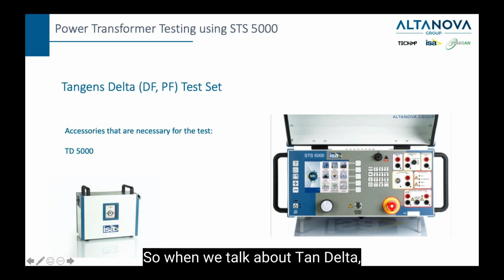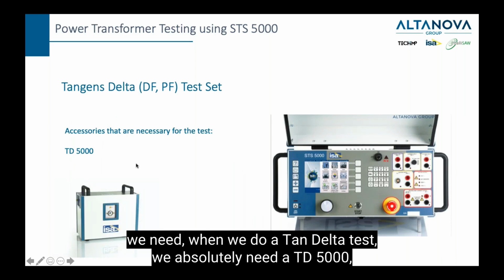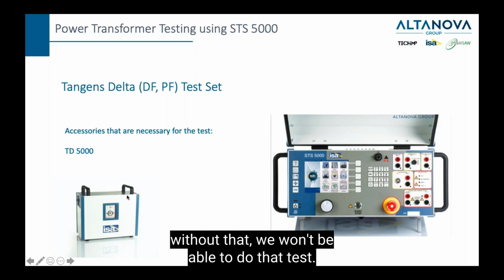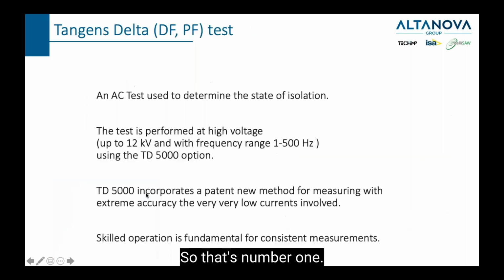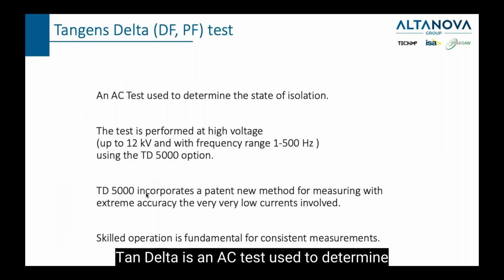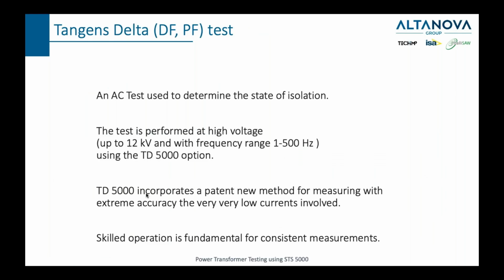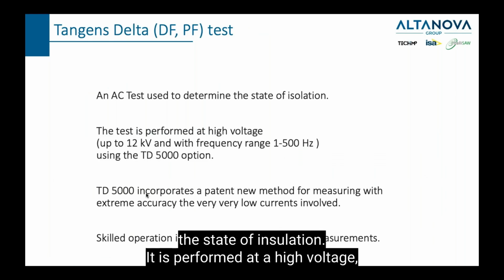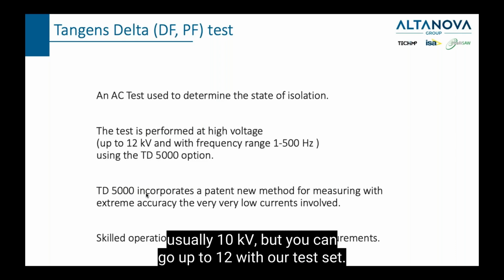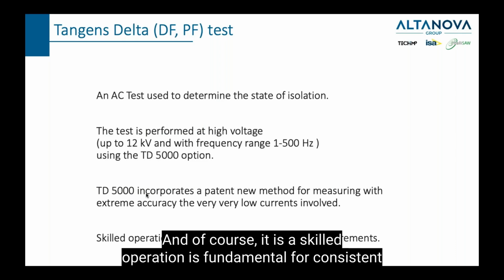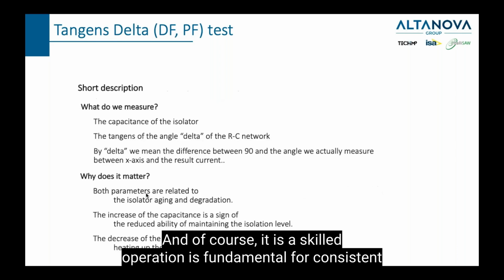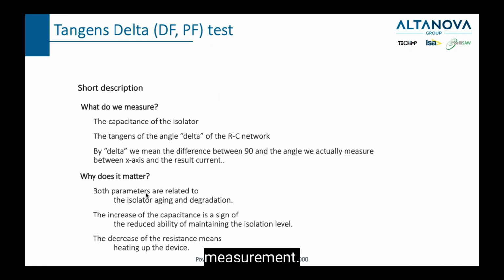So when we talk about tan delta, when we do a tan delta test, we absolutely need TD5000. Without that, we won't be able to do that test. So that's number one. Tan delta is an AC test used to determine the state of insulation. It is performed at a high voltage, usually 10 kilovolts, but you can go up to 12 with our test set. And of course, it is a skilled operation, which is fundamental for consistent measurement.